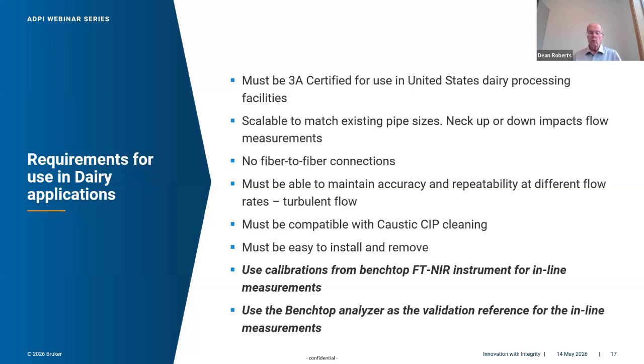And one of the things that we found with the fiber optic probes that we've been using to date is they use internal fibers to move the light through the sampling gap and then back up to the instrument. And when you have two parallel surfaces that are separated by something that has a different refractive index, in this case air, you get what's called interference fringing. So it's a cosine wave pattern that sits on top of the spectrum.